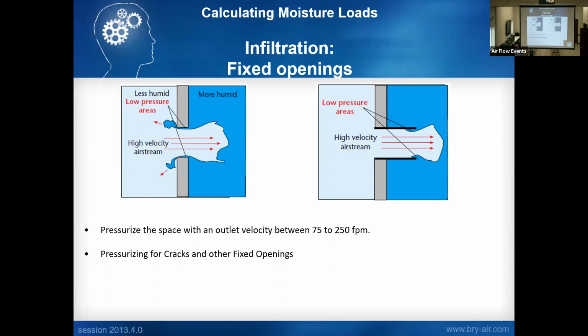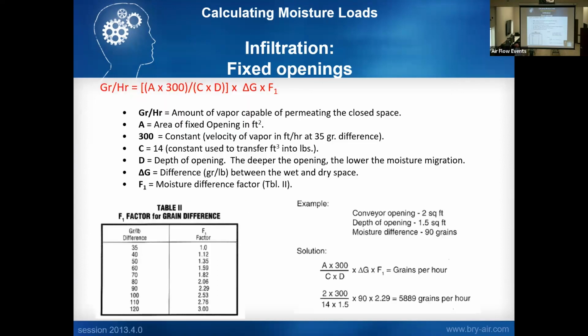Here you got some ways we deal with those to reduce that amount of moisture. One is pressurization. Get some high velocity airstream through that opening whenever you can. Kind of difficult on conveyors because when you deal with the conveyor, you got to look at product weight and everything. You don't want to just shove 1,000 feet per minute of air through an opening and blow the product off the conveyor. So you got to pay attention to that. Another thing that we do is basically build like a tunnel around that opening. The longer the tunnel, the less moisture that infiltrates. So, typically tunnels for conveyors, we typically do about 2 or 3 foot into the more humid space. Again, here's a calculation for that infiltration.